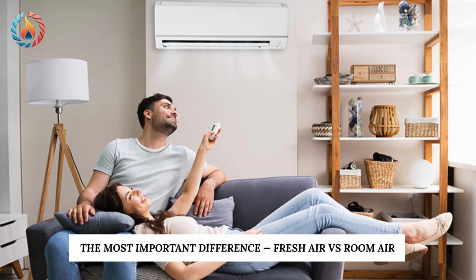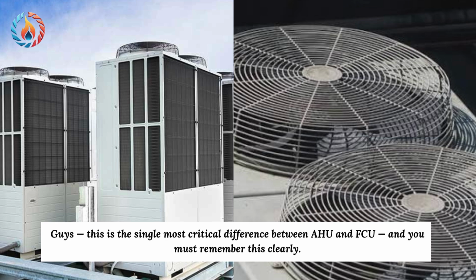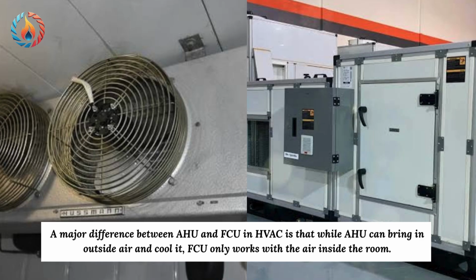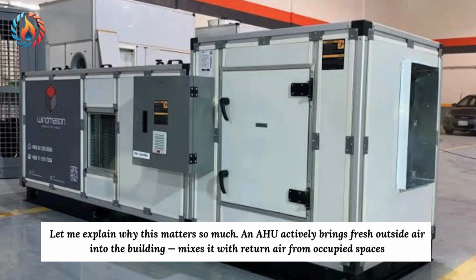The most important difference: fresh air versus room air. Guys, this is the single most critical difference between AHU and FCU, and you must remember this clearly. A major difference between AHU and FCU in HVAC is that while an AHU can bring in outside air and cool it, an FCU only works with the air inside the room. Let me explain why this matters so much.